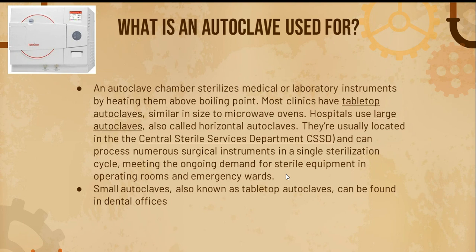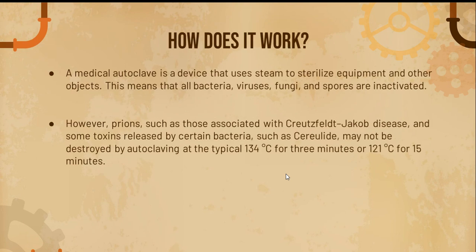Small autoclaves, also known as tabletop autoclaves, can be found in dental offices. So how does it work? A medical autoclave is a device that uses steam to sterilize equipment and other objects. This means that all bacteria, viruses, fungi, and spores are inactivated. However, prions such as those associated with Creutzfeldt-Jakob disease and some toxins released by certain bacteria such as cereulide may not be destroyed by autoclaving at the typical 134 degrees Celsius for 3 minutes or 121 degrees Celsius for 15 minutes.